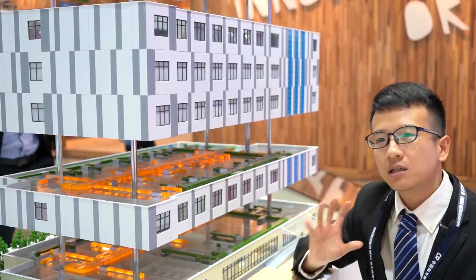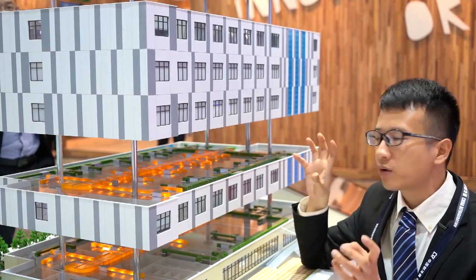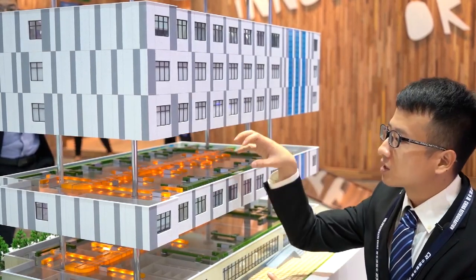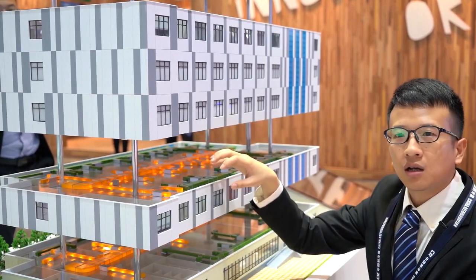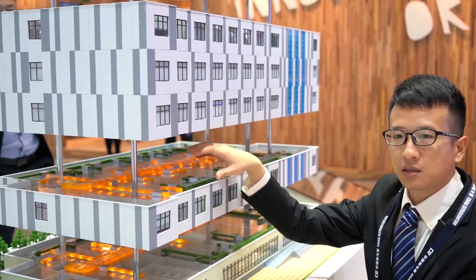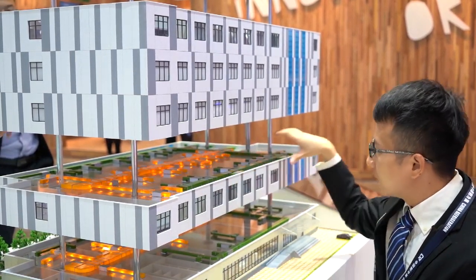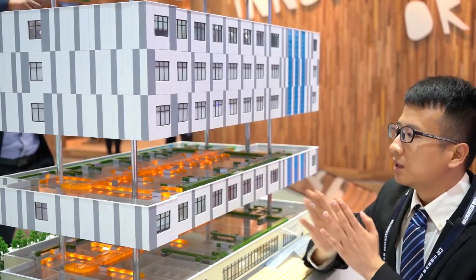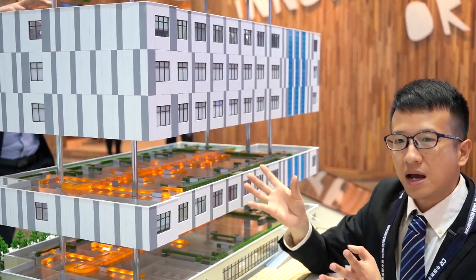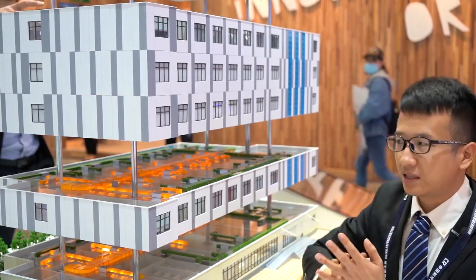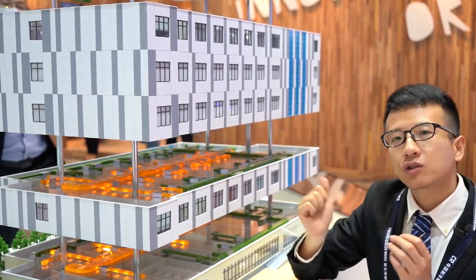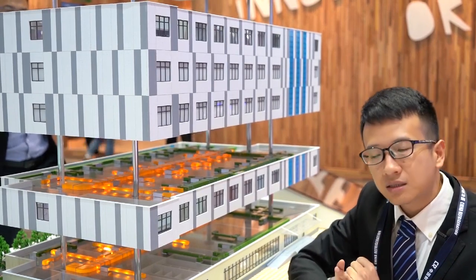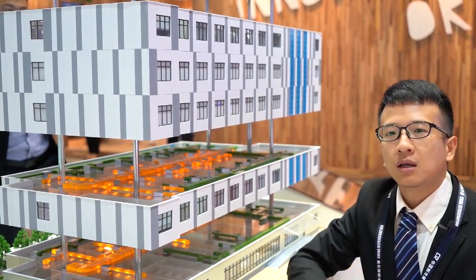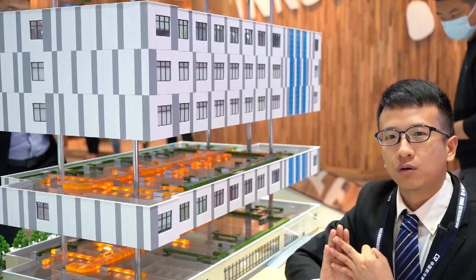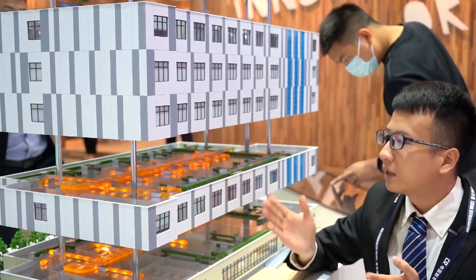So we have to consider the air pressure in each room during our design of the supply air ductings and exhausting air ductings system in this floor. And of course, I'm only taking this floor as an example. The principle is the same for all the floors. We have to consider the air cleanliness, room pressure, and the minimum fresh air flow. That is how we design the air ductings in this part.